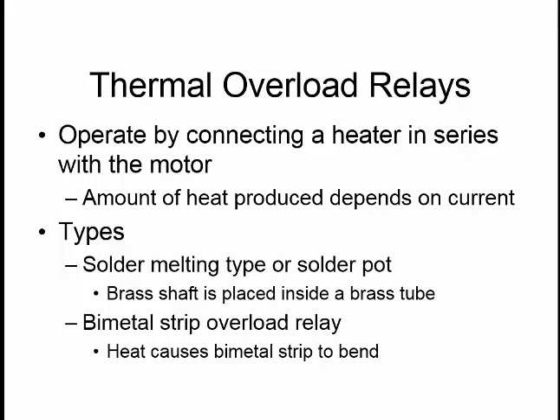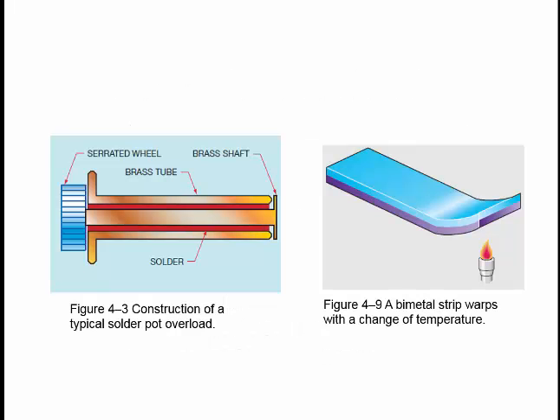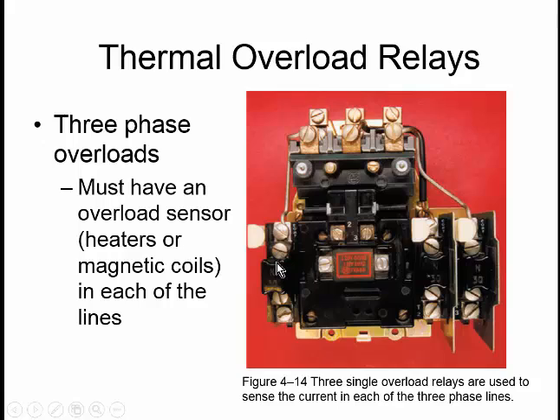A thermal overload is a little unit that's put in series with the motor load, and if it gets warm enough, it trips a set of contacts. There are a couple of different types: a melting type and a bimetal type. These are older; if you buy anything new, it'll be electronic. But you'll see them in older setups, and you'll see them in the lab too. So here are these mechanical types. This is the type where you have something in a tube that melts, and then it gets solid after it cools. And this is the bimetallic strip, two different metals that expand at a different rate when heated, which causes the strip to warp and trip. Thermal overloads are put in every phase. If you have a three-phase motor, there's one in each of the three phases.